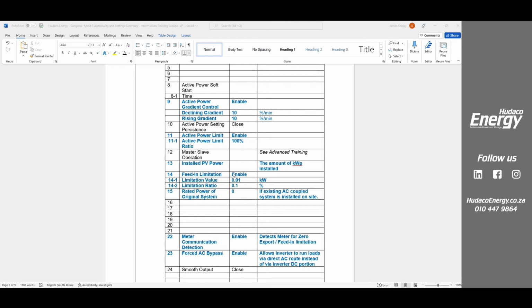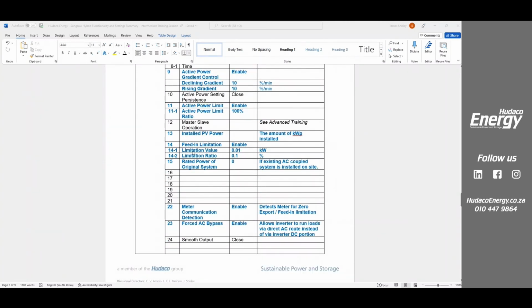If you've got one of those rotary meters, well, we're required to tell you that you're not allowed to feed in, but we've got clients where, for some reason, this keeps changing itself automatically. We're not sure how. Set these limits to 0.01 kilowatts and your feed-in limitation ratio to 0.1%, and we see no feedback then. This one here, number 15, the rated power of the original system. Okay, this is if there's an already installed string inverter on site that's running, say, 3 kilowatts, 6 kilowatts, 8 kilowatts, whatever it is. This is where you would put this. This is for an AC coupled system only.